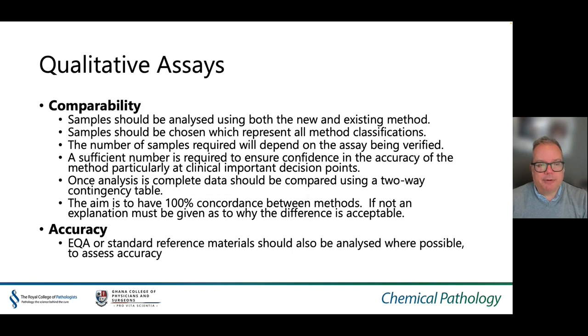Qualitative assay verification and validation essentially follows the same procedures outlined. In terms of comparability there are some differences: samples should be analysed using both the new and existing methods, and samples should be chosen which represent all method classifications. A sufficient number is required to ensure confidence in the accuracy of the method, particularly at clinically important decision points. Once analysis is complete, data should be compared using a two-way contingency table, with the aim of achieving 100% concordance between the two methods. If not, an explanation must be given as to why the difference is acceptable.